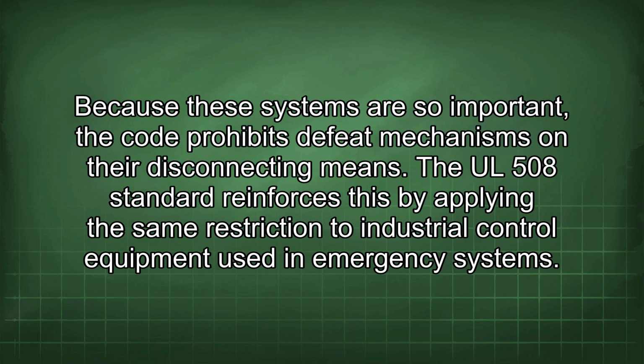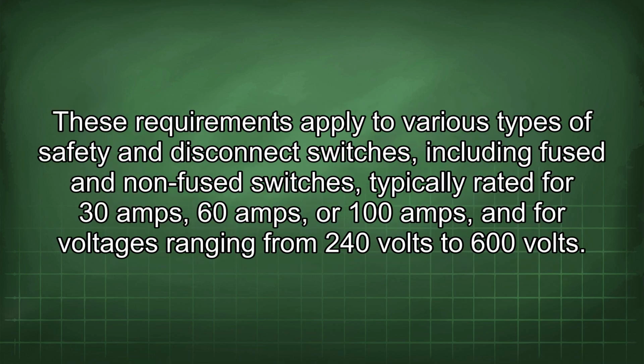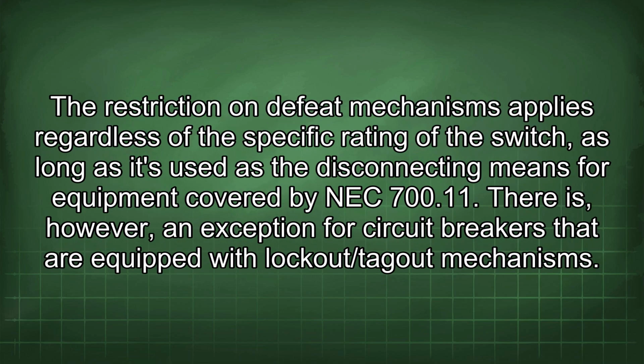The UL 508 standard reinforces this by applying the same restriction to industrial control equipment used in emergency systems. These requirements apply to various types of safety and disconnect switches, including fused and non-fused switches typically rated for 30 amps, 60 amps, or 100 amps, and for voltages ranging from 240 volts to 600 volts. The restriction on defeat mechanisms applies regardless of the specific rating of the switch, as long as it's used as the disconnecting means for equipment covered by NEC 700.11.